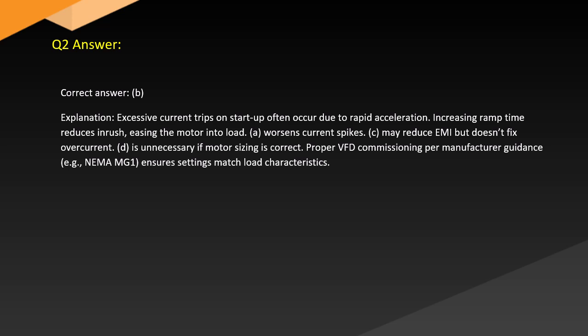Answer. Correct answer: B. Explanation. Excessive current trips on startup often occur due to rapid acceleration. Increasing ramp time reduces inrush, easing the motor into load. A worsens current spikes. C may reduce noise but doesn't fix overcurrent. D is unnecessary if motor sizing is correct. Proper VFD commissioning per manufacturer guidance, e.g. NEMA MG1, ensures settings match load characteristics.